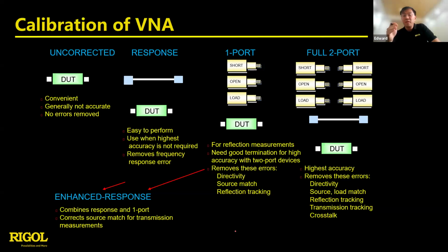So you need to do some very complicated calibrations. Some vendors also provide eCals, which can save your time doing the calibration procedures, especially for multi-port tests. Okay.